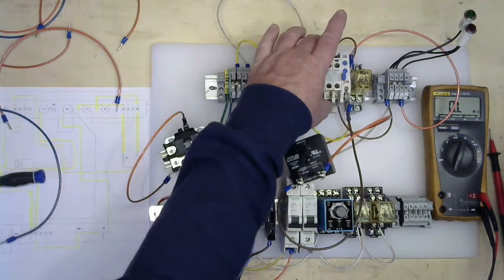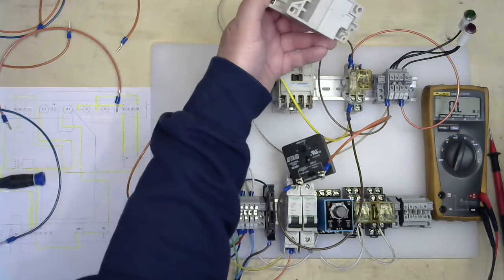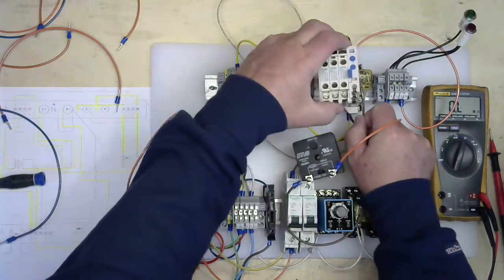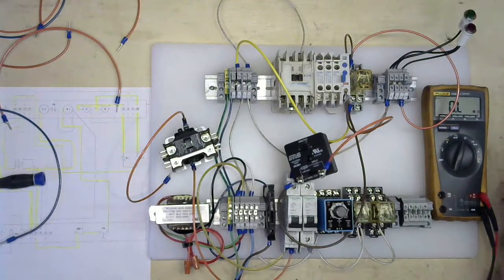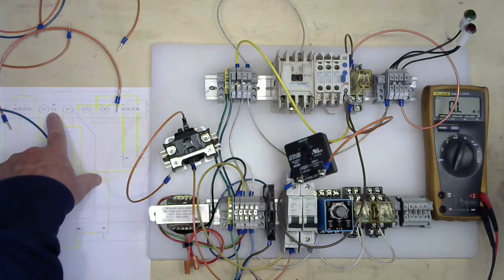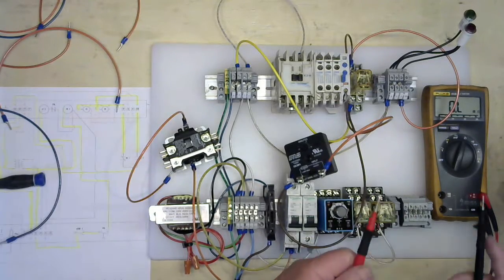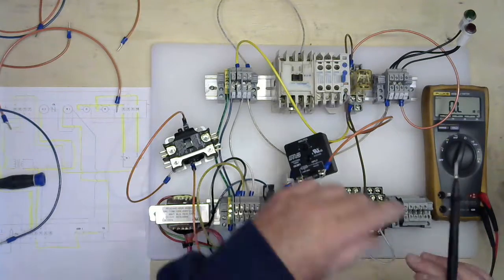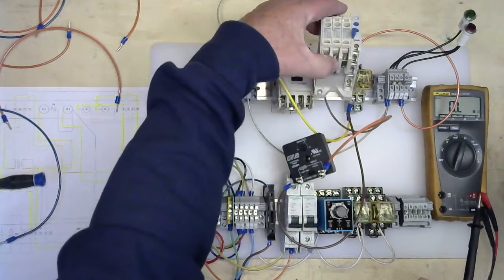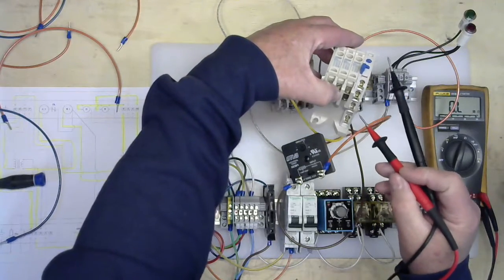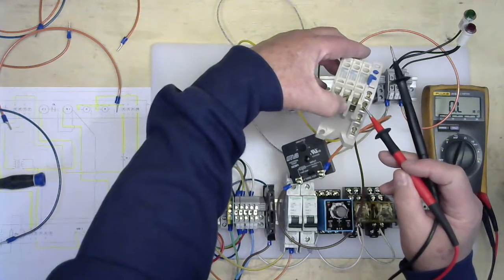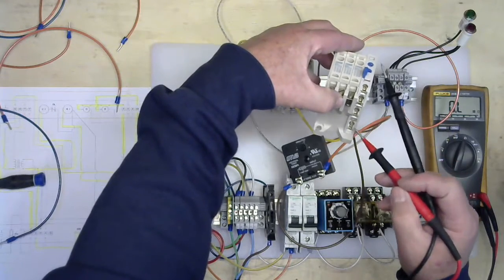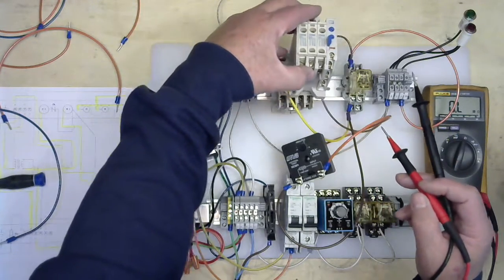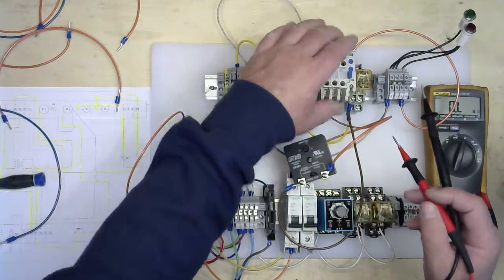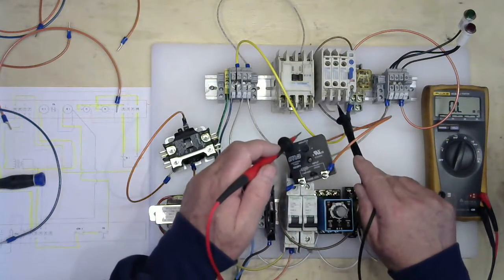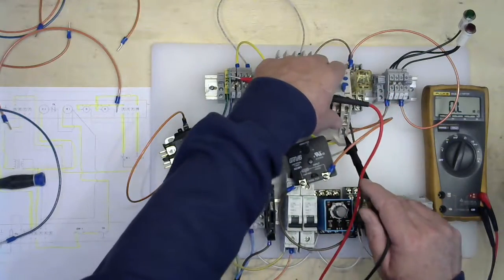Now here is my overload, and you can see this one does not have a DIN rail on the bottom of it, so for this particular one I have to lay it in place. So the question is, we want to make sure that we get our normally closed contacts. So while our meter is still on ohms, using the 4 different terminals, usually ones are grouped together, or one set of contacts, open or closed, and the other ones are the opposite. So I'm going to have to determine, placing my meter on the bottom contacts.